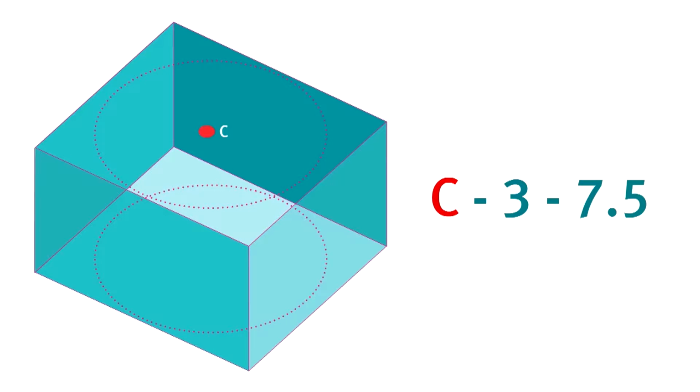A ceiling mounted VAD might be rated as C37.5, where C stands for ceiling. The 2 numbers represent the coverage volume in the shape of a cylinder, where the first number is the maximum ceiling height the VAD can be mounted, and the second number is the diameter of the coverage.